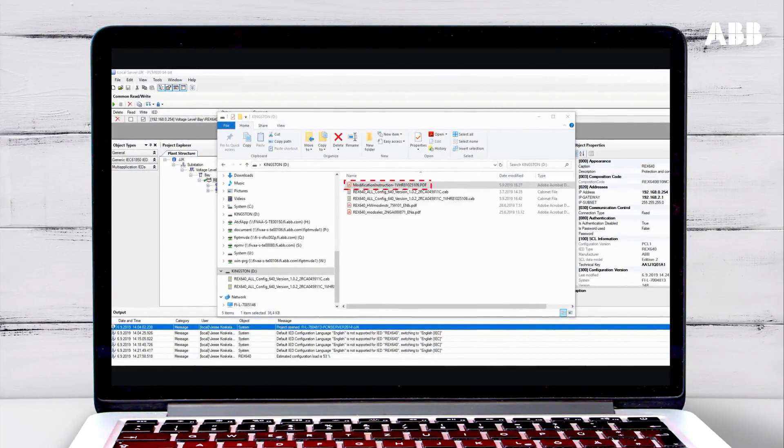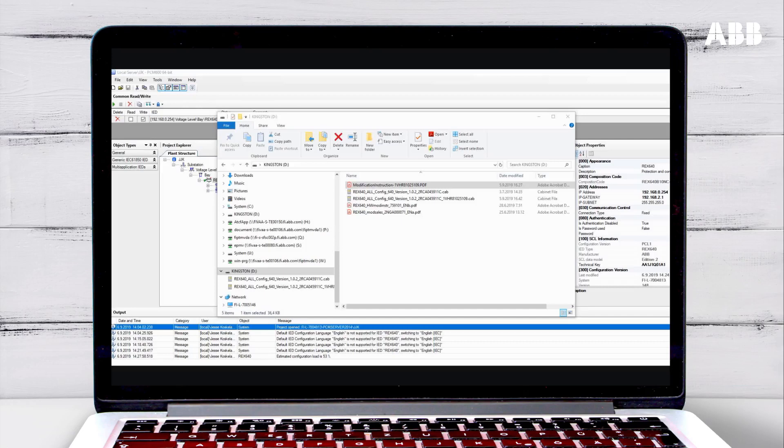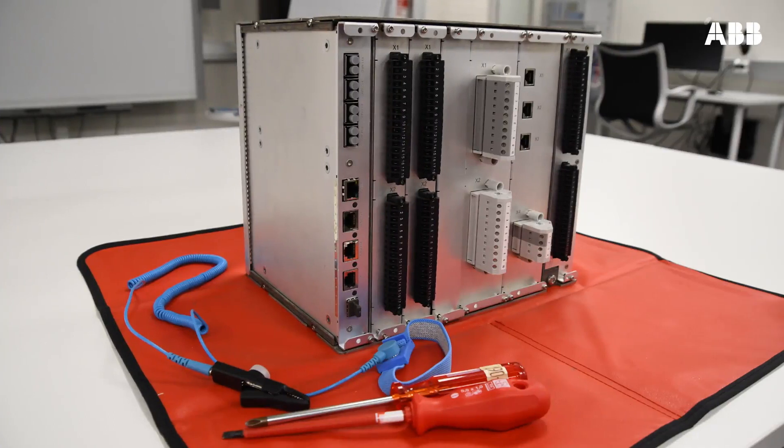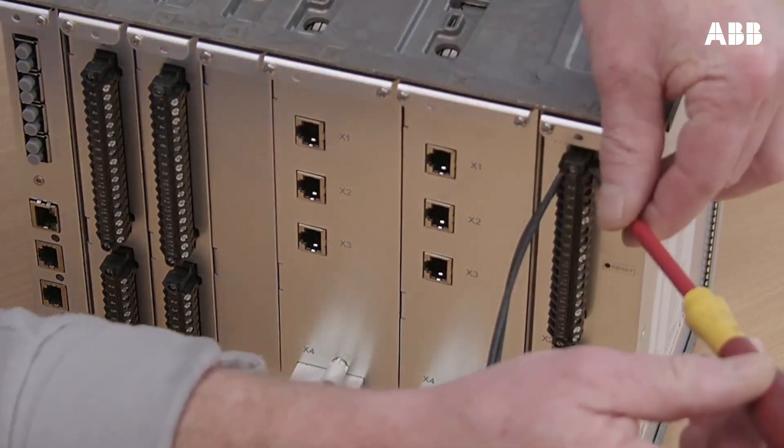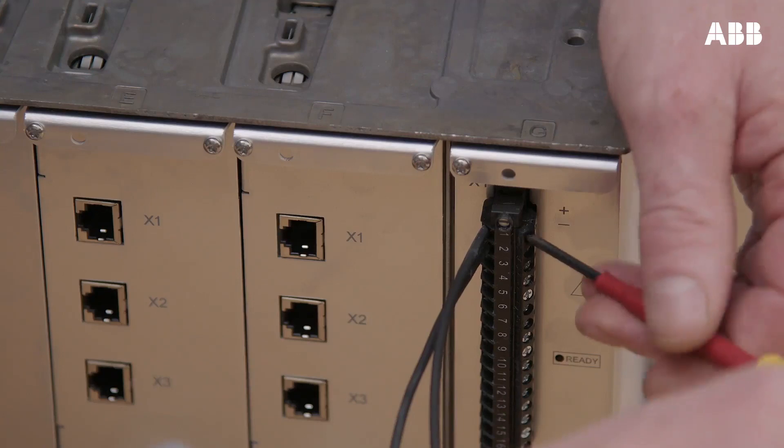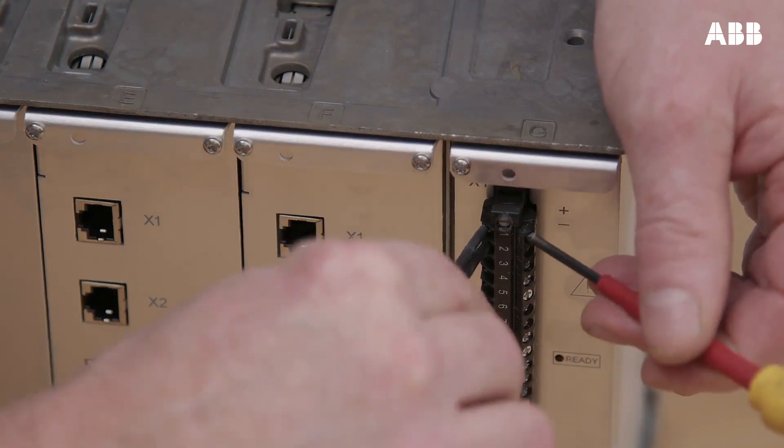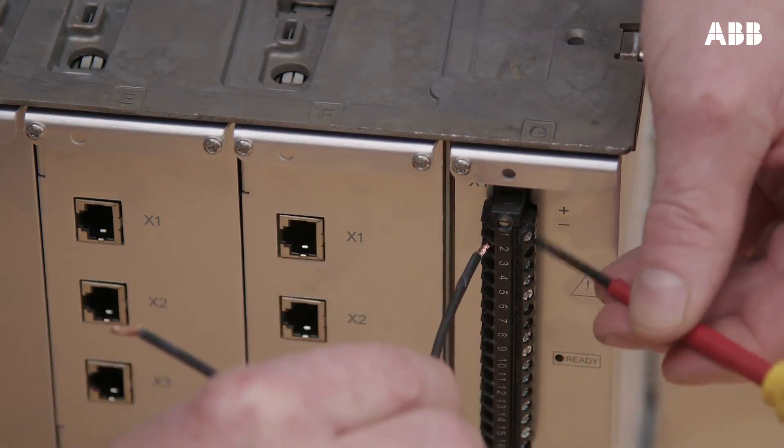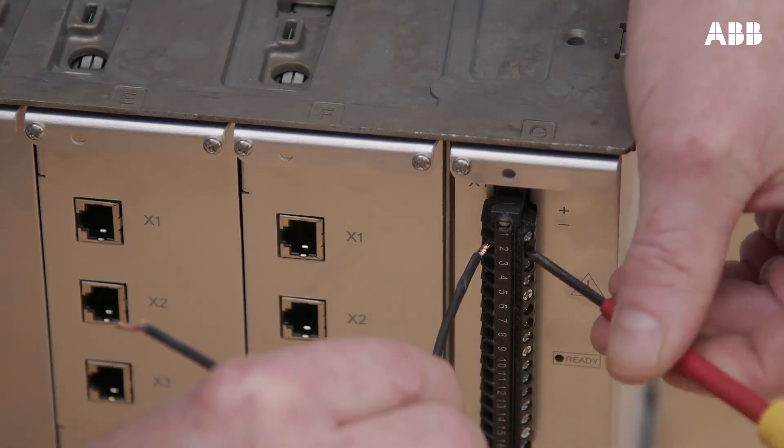Hardware modification instructions are included and explain the required tools and information needed to physically install the hardware module. Before installing the module, disconnect the relay's auxiliary voltage and make sure that you are carrying out modifications on a de-energized feeder.